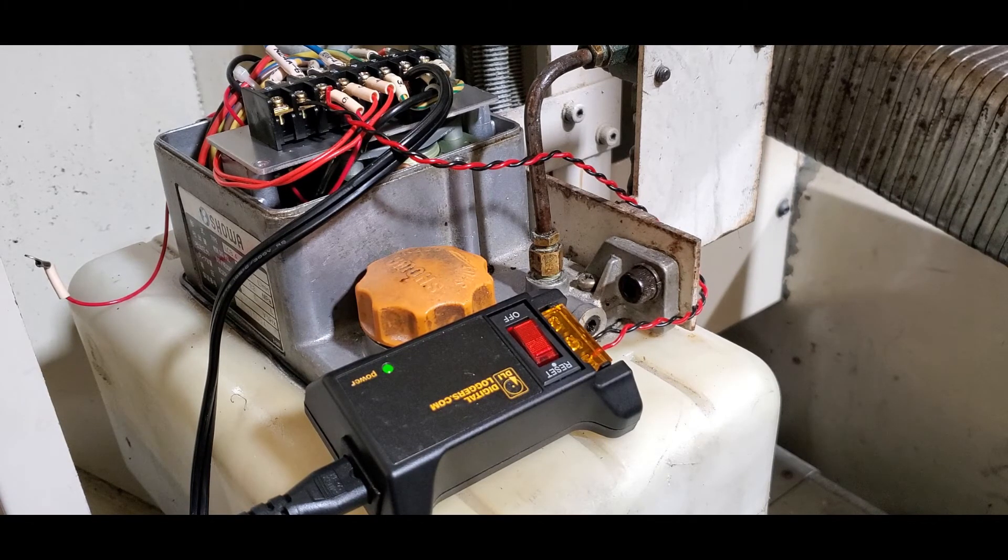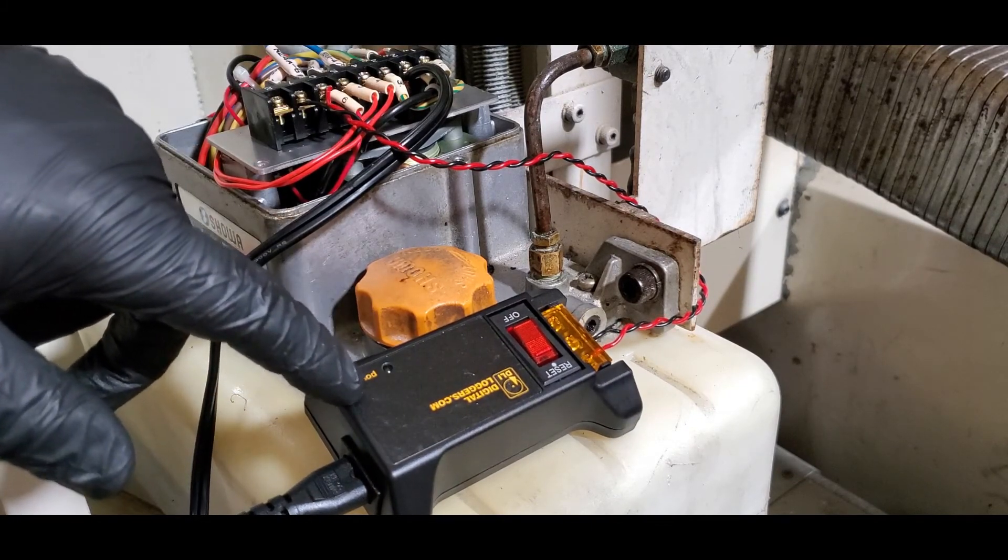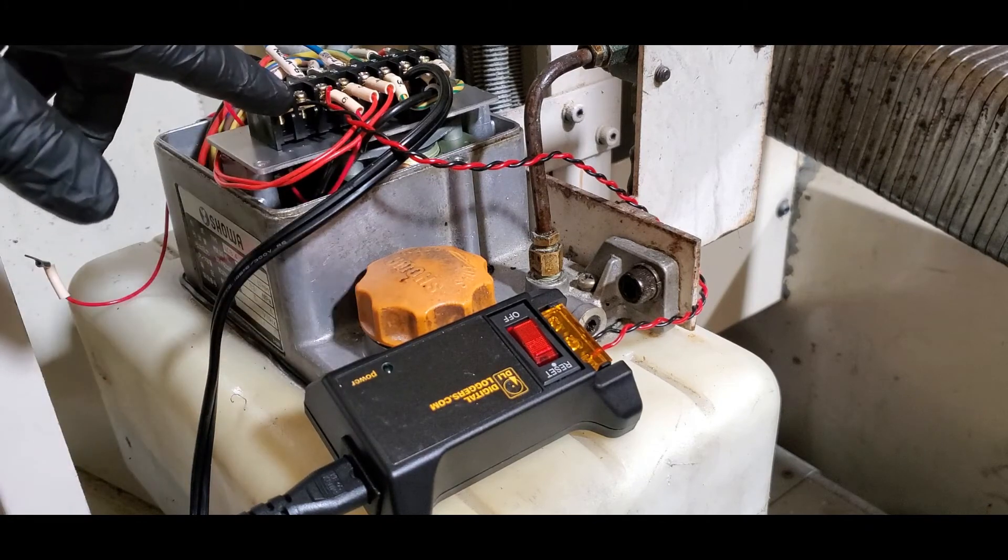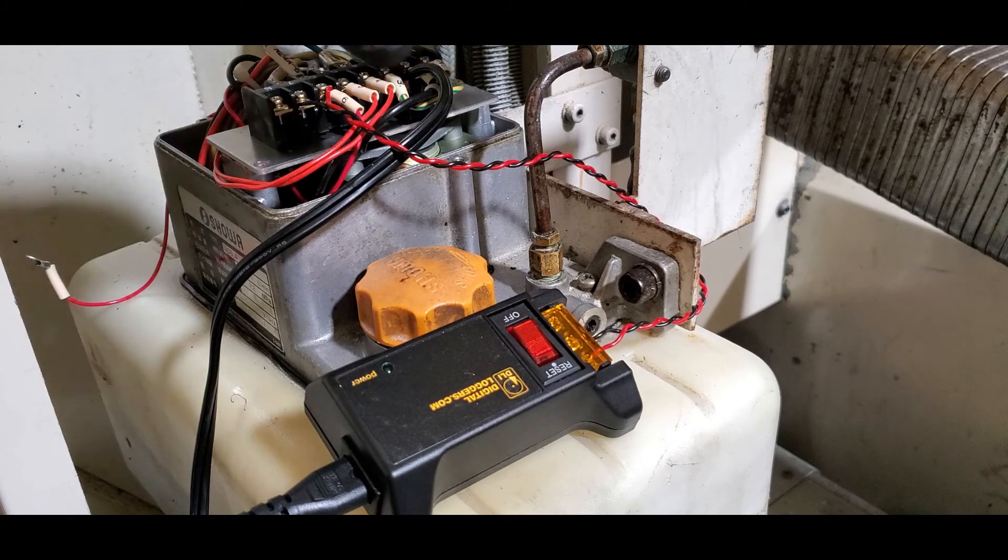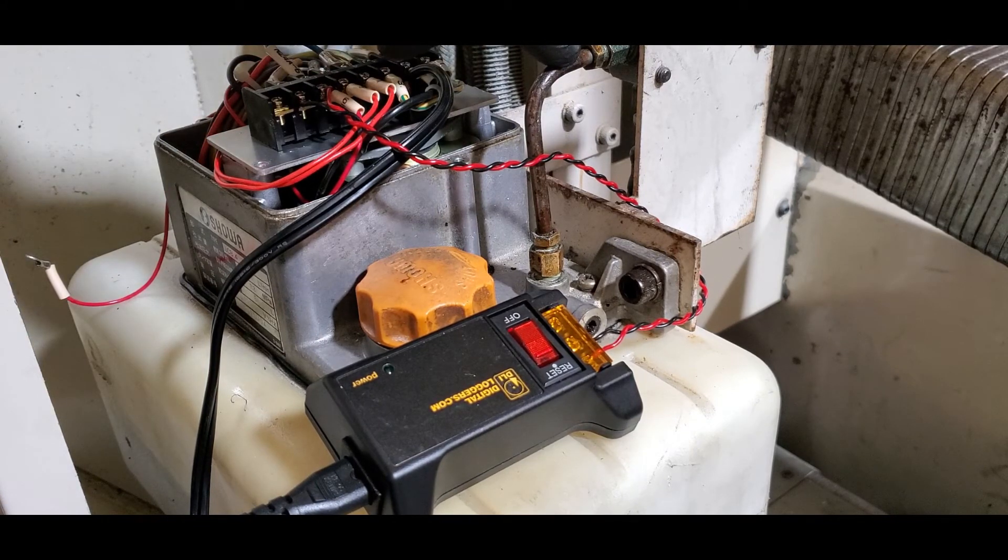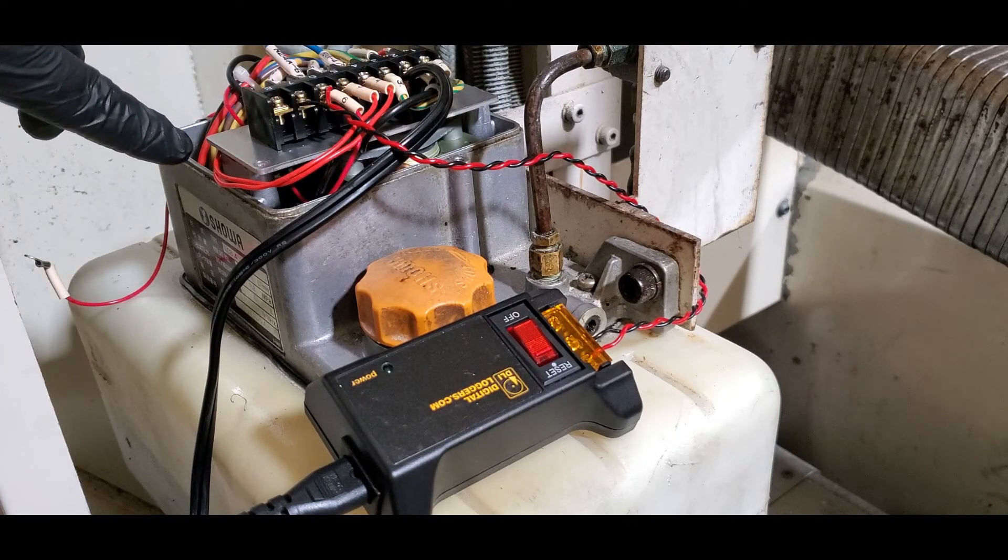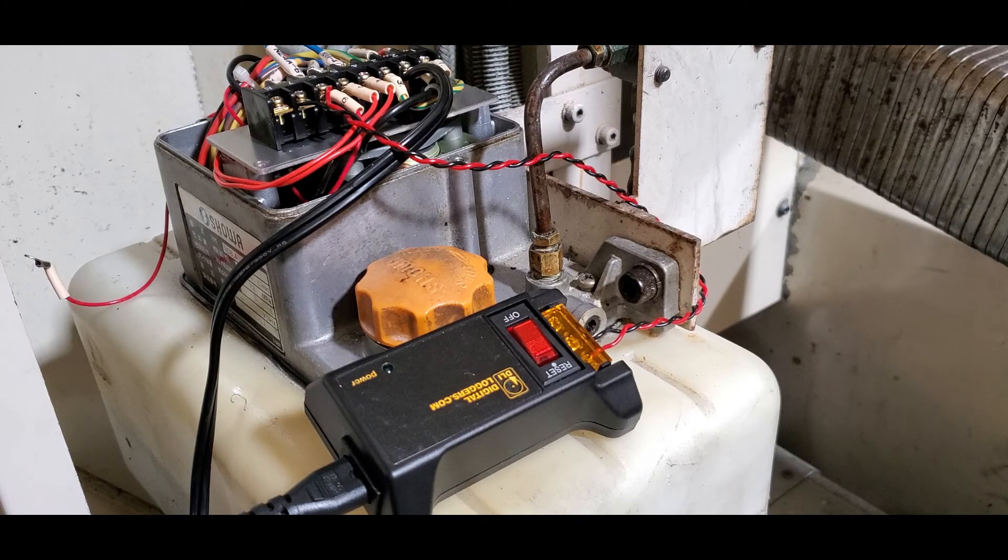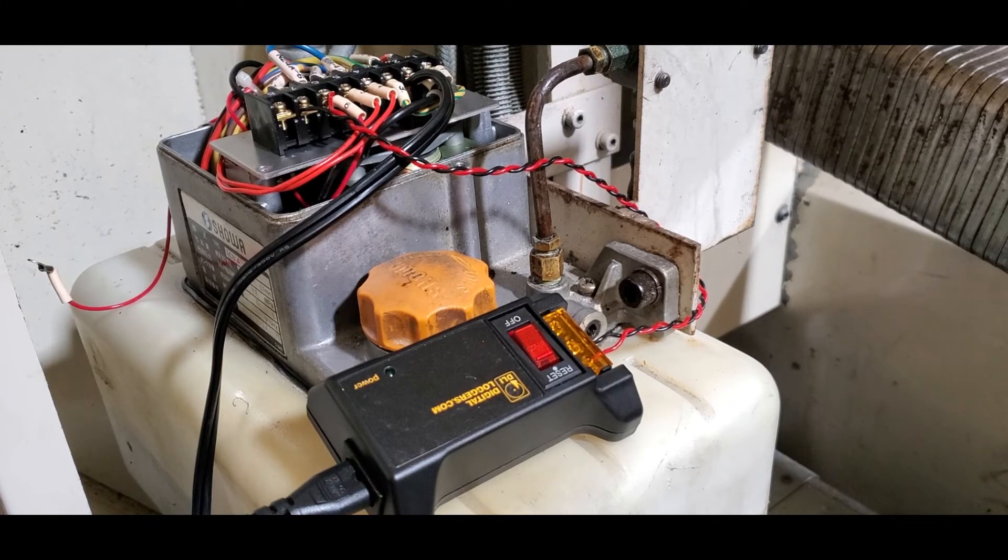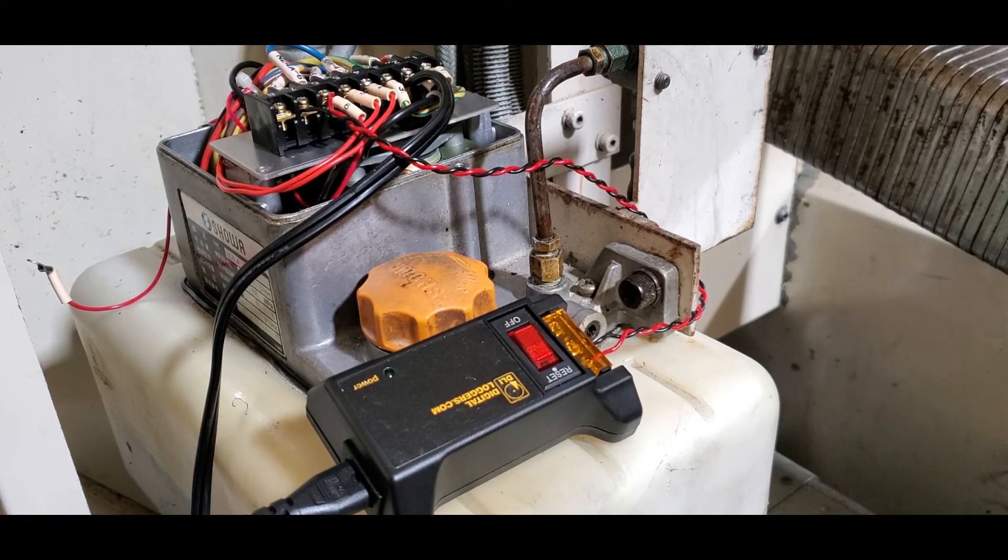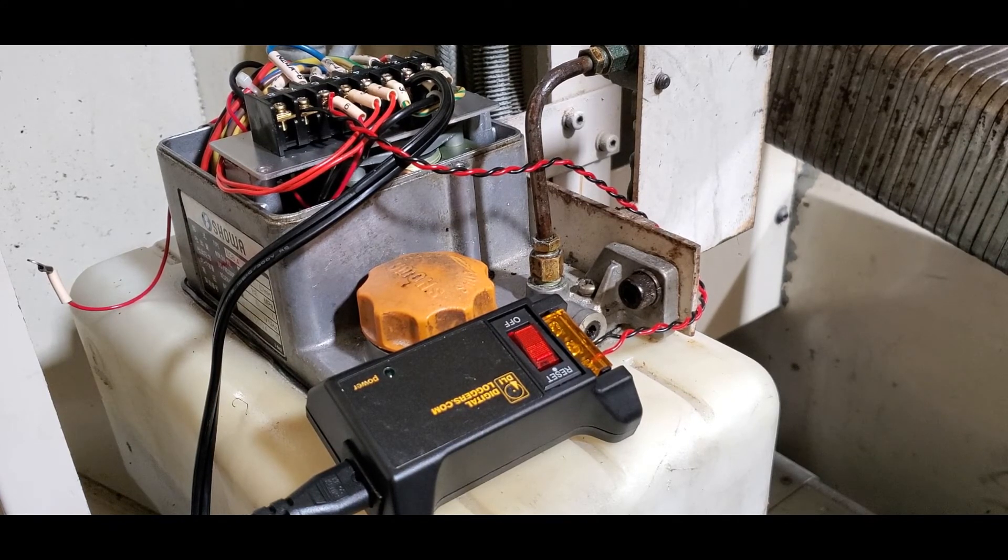So now the motor is turned off, it has turned this off and killed the switch. So that should act exactly how it should. Now, like I said, we pulled this off and capped it. So there was nowhere for the oil to go other than the switch down here. And it didn't have enough pressure to push that switch up. So I've got to look at, so I think there's something wrong in the pump area itself. Everything is running. But I don't know.